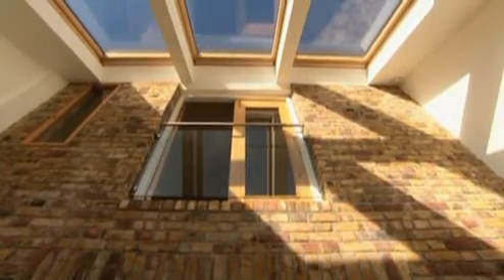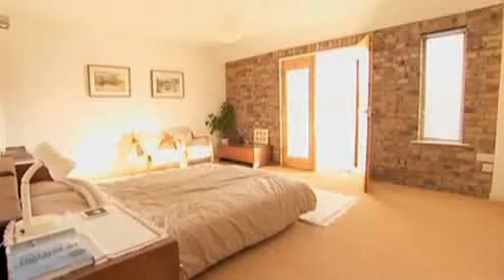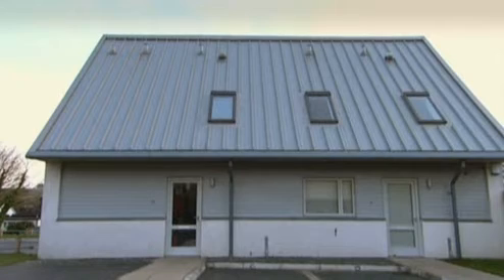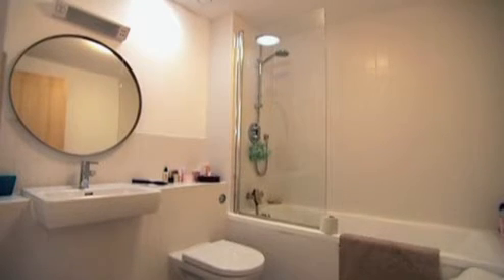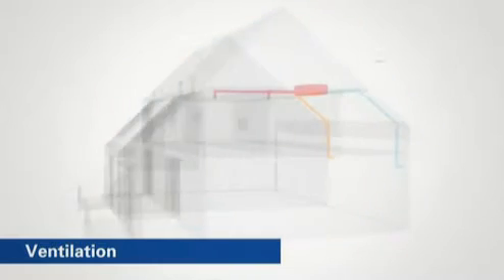The homes benefit from passive design. Huge southeast-facing windows capture the warmth of any sunshine and provide plenty of natural light, while underfloor heating does away with the need for radiators, leaving uninterrupted wall space which makes each room spaciously stylish. We designed them with a certain amount of thermal mass, as we felt that was key to retaining the heat. We also built a very highly insulated, relatively airtight skin. When you seal up a house like that, you can develop problems with stale air and moisture, so we've introduced a heat exchange ventilation system, which overcomes that problem. The ventilation units supply fresh air while extracting damp or stale air from bathrooms and kitchens, and the incoming fresh air is slightly preheated by the heat exchanger so it doesn't result in cold drafts.